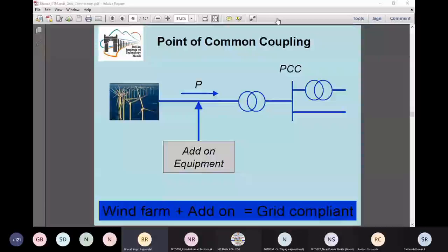Yeah. So this is what it is saying: if a wind farm is working at 100%, it means if a wind farm is having 5 MVA of one wind turbine and it is working at 5 MVA, it is working at 100%. So if the frequency is going beyond 50.3 hertz, then it is expected that the output of this wind farm, which is 5 MVA, should be reduced at that particular ramp rate or below that.